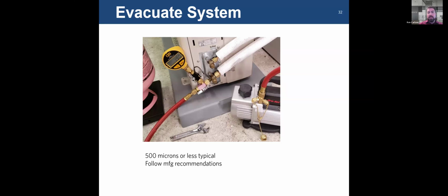You need to get all the non-condensables out. They'll react and cause problems inside the system, or take up space and reduce your capacity. So regardless, we need to pull a vacuum and get all oxygen, all air, all moisture out of these lines and out of the indoor unit, so that when we do open these valves, there's nothing but refrigerant in the system. You'll need to pull down below 500 microns. That's the typical industry standard. Some manufacturers will require another number to pull down further than 500. You'll need a micron gauge, because your regular gauges won't show you microns. You pull your vacuum down to below 500.